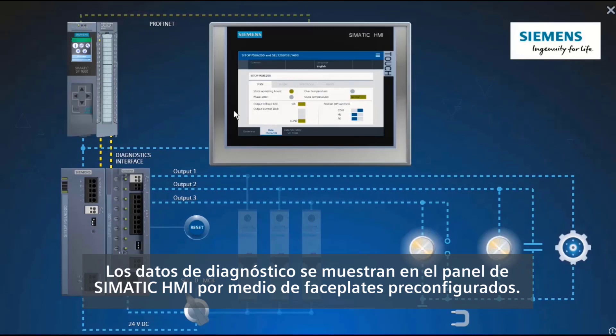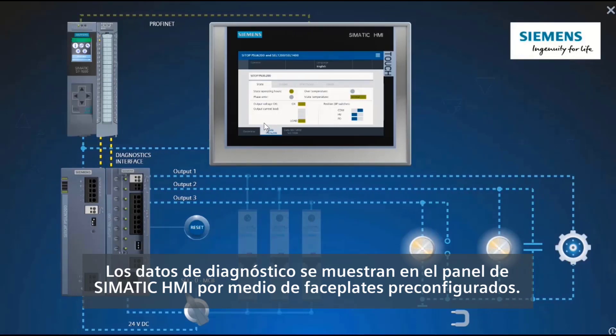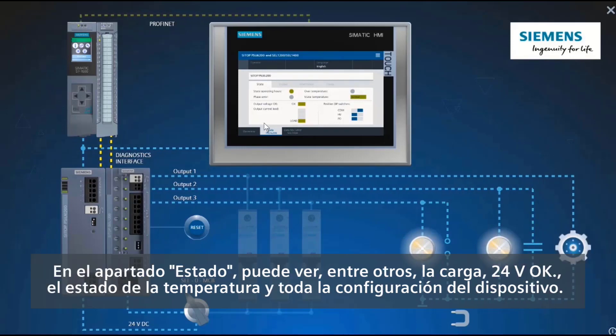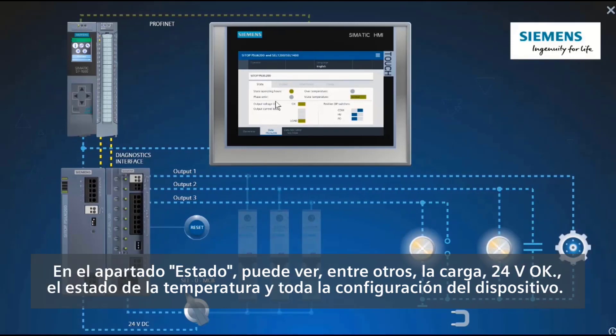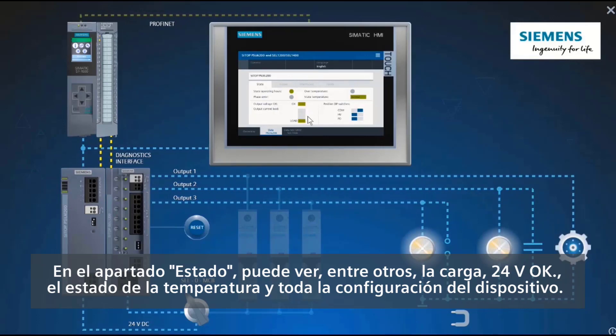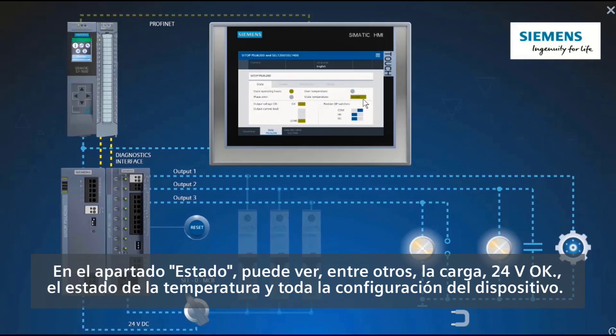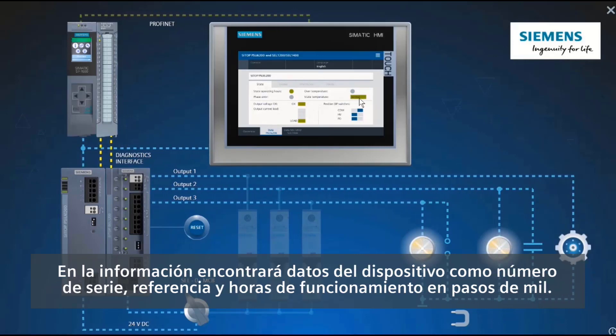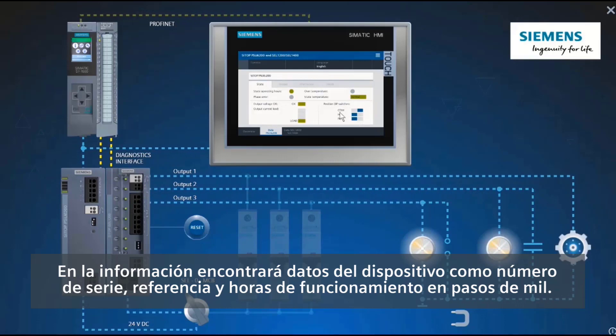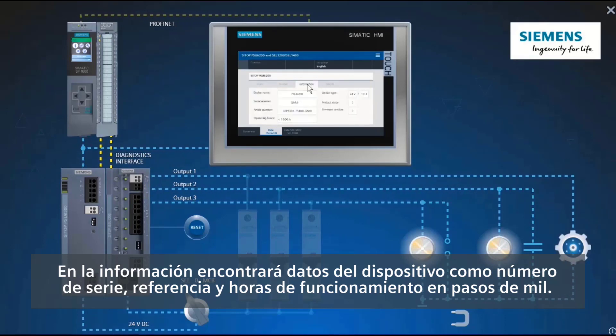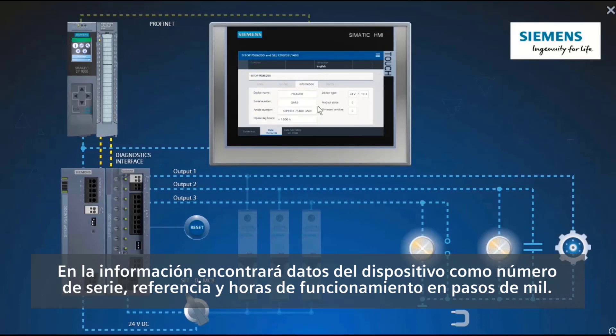The diagnostics data is simply displayed on the SIMATIC HMI panel by means of ready-made faceplates. Under the heading Status, you can see, for example, the load 24-volt OK, the temperature status, and all the device settings. Under Information, you will find device data such as serial number, article number, and the operating hours in steps of 1000.